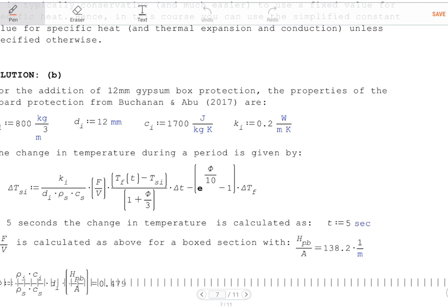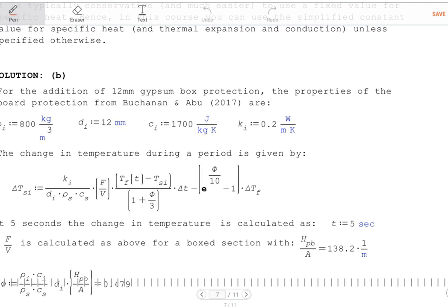For instance, we estimate initially that 12 mm may be enough, and we would possibly require a couple of iterations to get this right. But for the addition of a 12 mm gypsum box protection, the properties of the board from Buchanan are as shown. So there are our properties of density, thickness, specific heat, and conductivity.